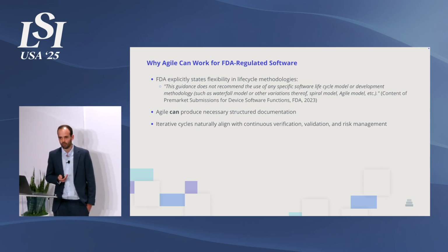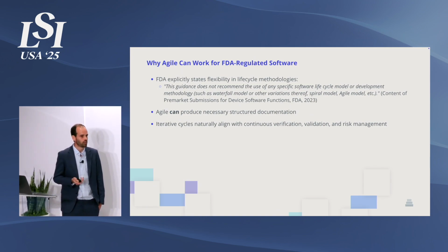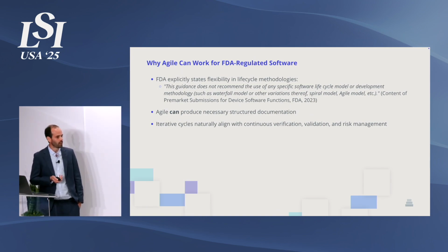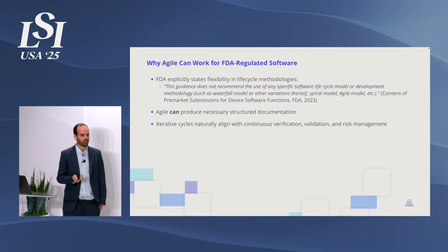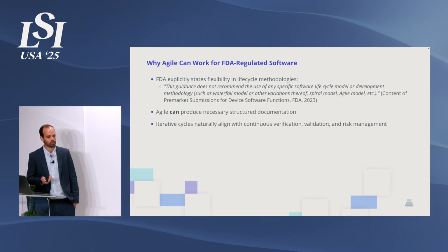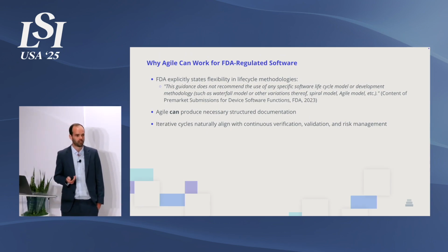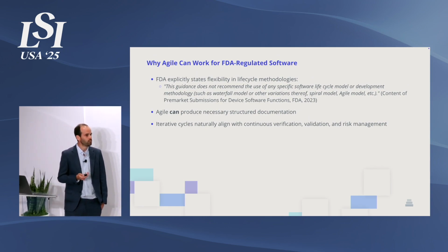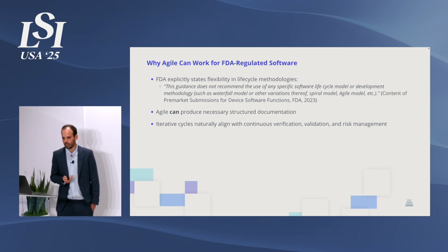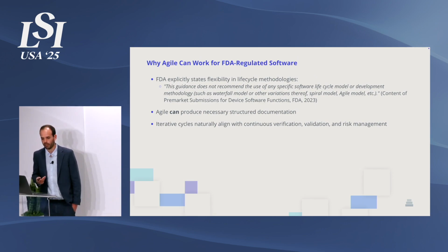The other thing is that we believe Agile can produce documentation that is structured and covers everything the FDA requires in terms of design controls. It is true that when Agile first came into existence, it came as an alternative to Waterfall, where documentation was very extensive, and the people that implemented Agile wanted to do less documenting. But when you apply this to the medical device space, it doesn't mean that you don't document extensively. It's just that you plan it and do it in another way.